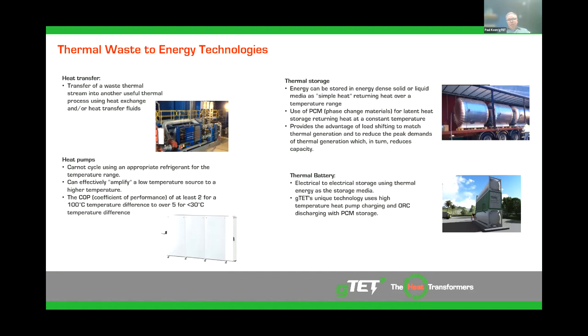Heat pumps allow low temperature waste streams to be economically lifted to higher, more useful temperatures. Thermal storage technologies allow for variable or intermittent waste or consumed streams to be stored and load shifted to match demand, thereby improving utilisation. The heat can be stored as simple heat, so the temperature reduces as heat is consumed, or latent heat in phase change material, so the temperature remains constant as the energy is consumed. Stored thermal energy can be sourced from and generated into electrical power, thereby providing a long duration, low cost thermal battery solution. And I'll discuss that a little bit more in a little while.